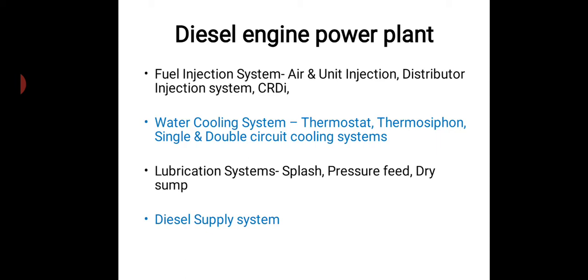For that, diesel is not economical. I think you are aware. This power what we buy at home costs somewhere around 6 to 7 rupees a unit, that is kilowatt hour on an average. But the same thing if you have a generator, like our college has a 62 kVA generator, and some shops have got generators. There when they generate power from petrol or diesel, it costs somewhere around 15 to 20 rupees per unit.